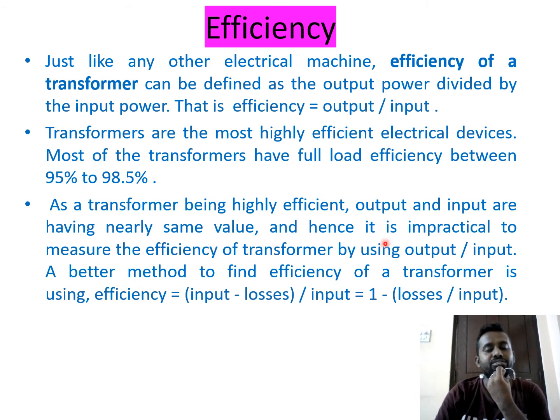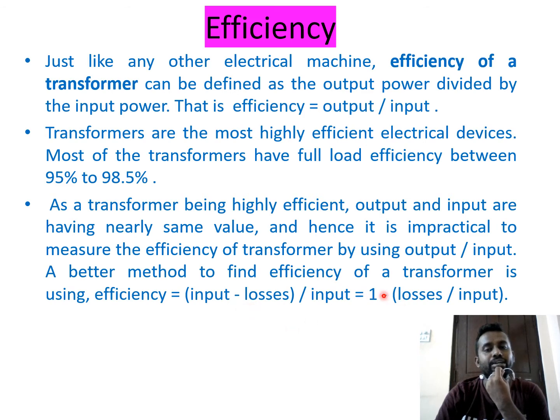Because output and input are nearly equal in a highly efficient transformer, it is impractical to measure efficiency by the direct output/input method. A better method is: efficiency η = (input − losses) / input = 1 − (losses / input), or equivalently, output / (output + losses).